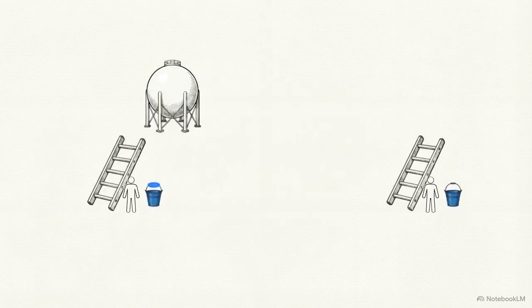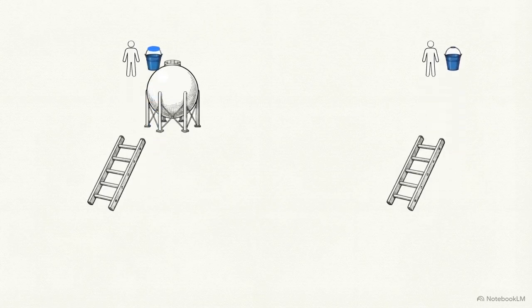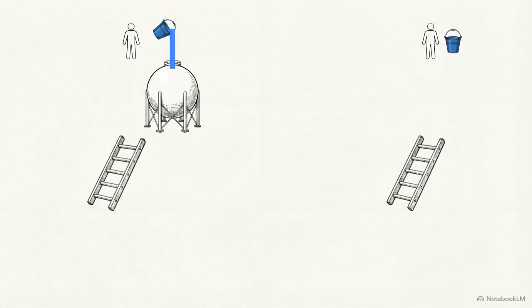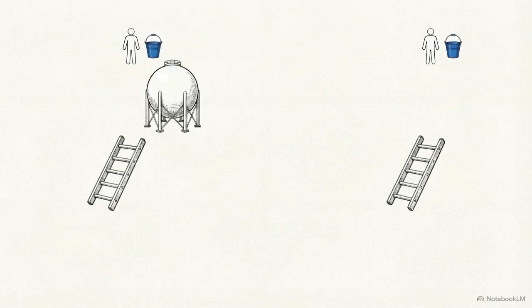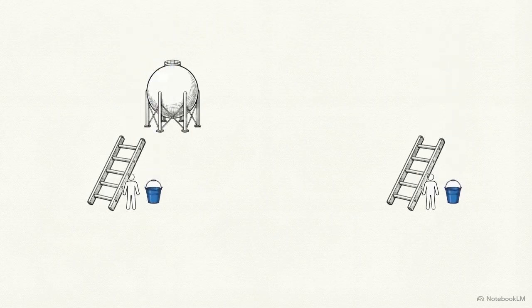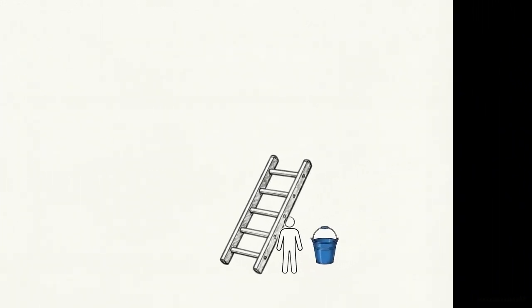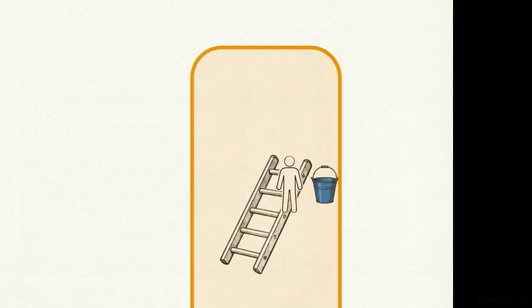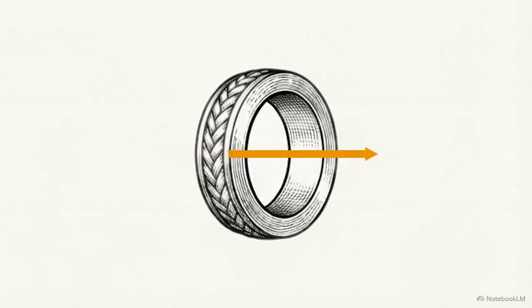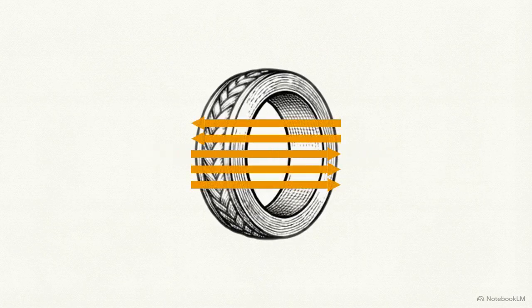Think of it like filling a water tower. If you carry a full bucket of water up a ladder and dump it in, you've done real work. That's real power. But if you carry an empty bucket up and down the ladder without ever dumping it, you haven't done any net work. That's reactive power. You still had to exert physical effort, and more importantly, you are taking up physical space on the ladder. Inside a transmission wire, reactive power takes up physical capacity, exactly like that person walking up and down the ladder. It creates a higher overall electrical current flowing through the metal, leaving less room for the real power we actually want to sell and use.